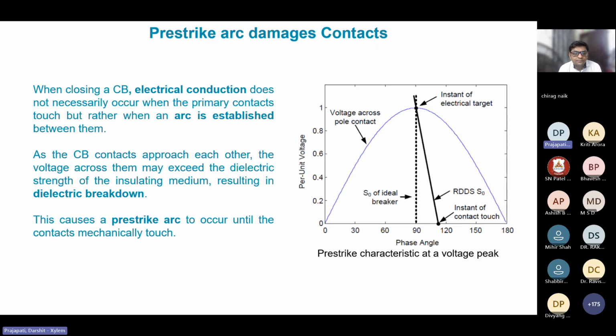Here, the pre-strike and the restriking arc are also important to understand. In general, they are particularly damaging near the current zero crossing, where the transient voltage peaks. These arcs repeatedly stress the contacts, reducing their life and reliability, and can even prolong the transient overvoltage into the network.